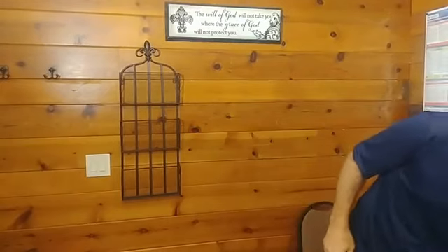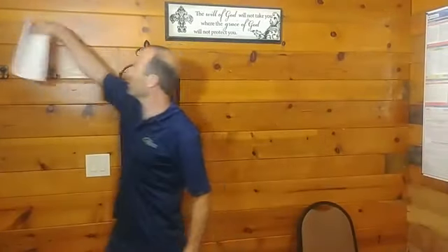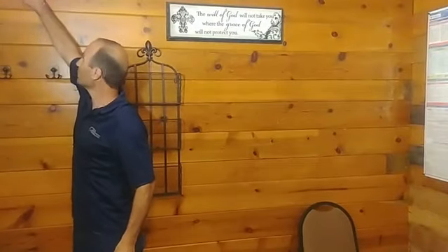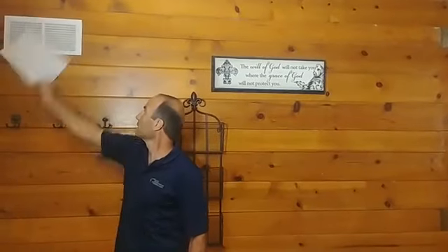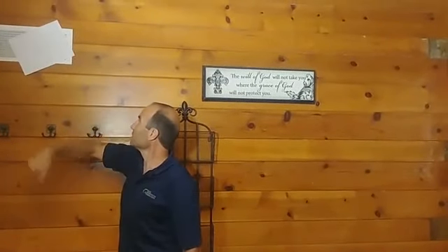One tip for you: if you're wondering if a cold air return is actually working well enough to do a good job, take a piece of paper, just a regular blank piece of paper, and stick it up on the cold air return. I don't even know if this is in the video. Can we see that? See how that paper just stays there? That's because the cold air is working. The suction is good. That means you're getting a good amount of suction through your return air. So those are good ways to test that.